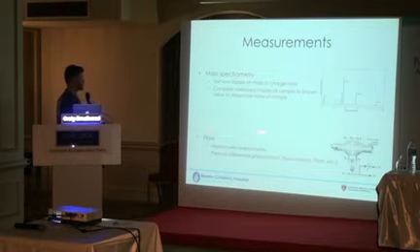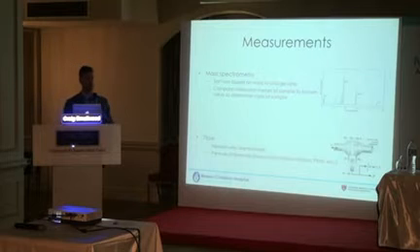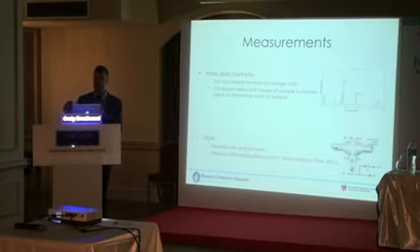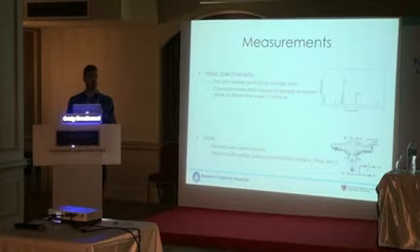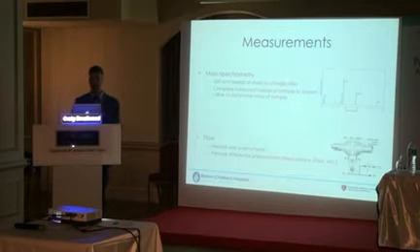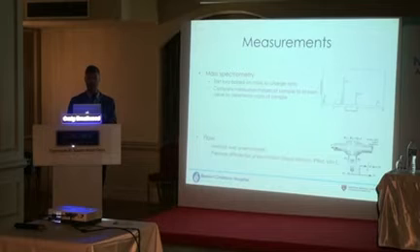And lastly, we need to measure flow, and this is really the same technology that's in ventilators. So there's all kinds of good technologies to assess flow rates, even in newborn children. Historically, I think we've had a lot of trouble as a field getting really accurate tidal volume and flow measurements in neonates because the tolerances just need to be so high that the technology just really wasn't there. But recently, even in these ventilators that do neonates to children to adults, have technology or proximal flow sensors that enable us to measure these things accurately and sufficiently for gas exchange purposes.